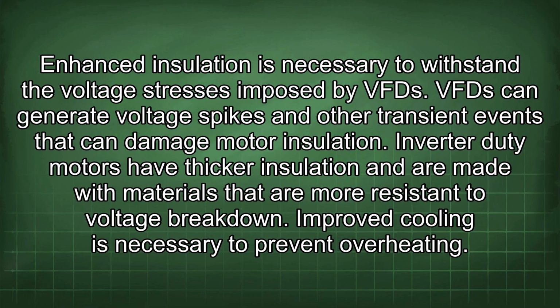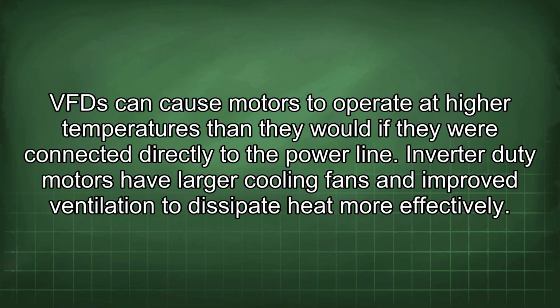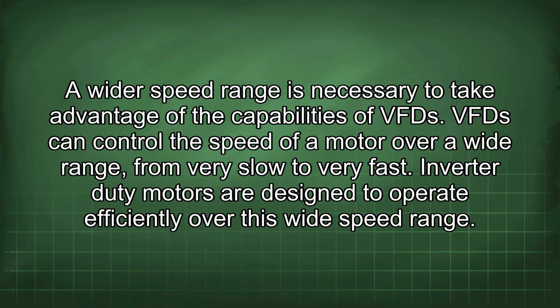Improved cooling is necessary to prevent overheating. VFD can cause motors to operate at higher temperatures than they would if they were connected directly to the power line. Inverter duty motors have larger cooling fans and improved ventilation to dissipate heat more effectively. A wider speed range is necessary to take advantage of the capabilities of VFD. VFD can control the speed of a motor over a wide range, from very slow to very fast. Inverter duty motors are designed to operate efficiently over this wide speed range.